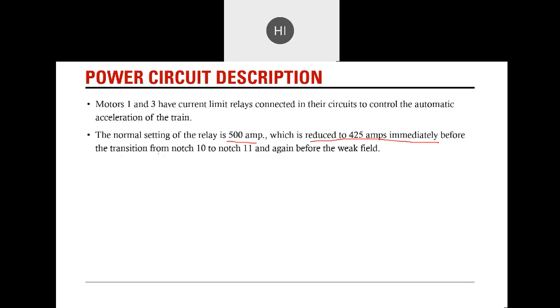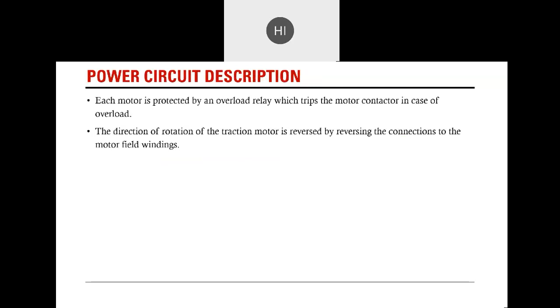ठीक है. देन मोटर 1 and 3 have current limiting relays connected to the circuit to control the automatic acceleration of the train. Okay, the normal setting of the relay is 500 amperes, which is reduced to 425 amperes immediately before the transition from notch 10 to notch 11 for weak field, okay. So ये जो current limiting relay है, again the purpose is to limit इस negative side पे जो हमारा current है उसको limit करने के लिए up to 500 amperes it has been given, okay.